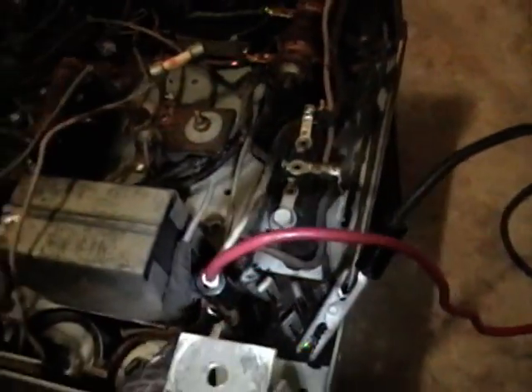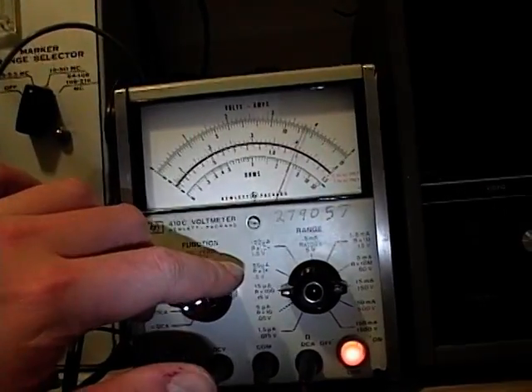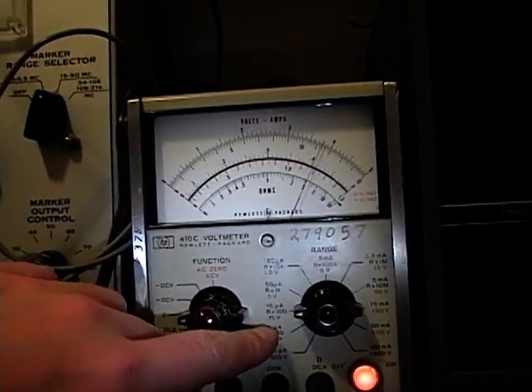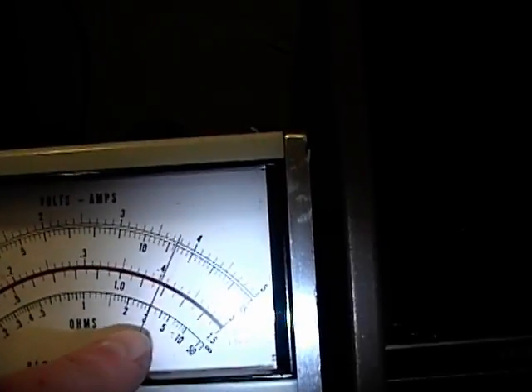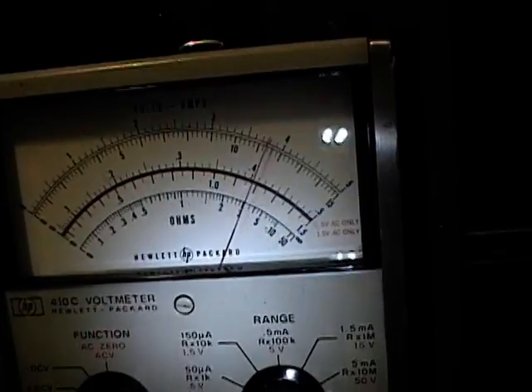By the way, I've taken all the tubes out, because if I left them in, the resistance of the filaments would affect my readings when I check the filament windings in the transformer. That's a good sign. Let's see - on the 100 range here, and it's reading about 300 ohms, so I would say that that's a very good reading.